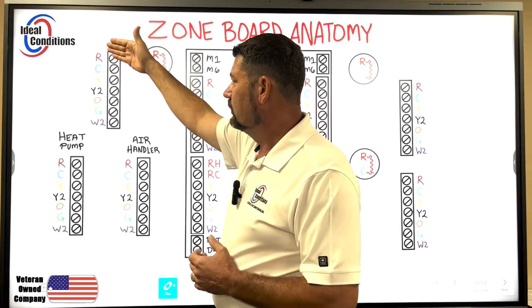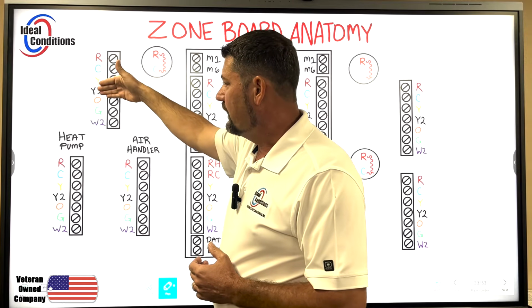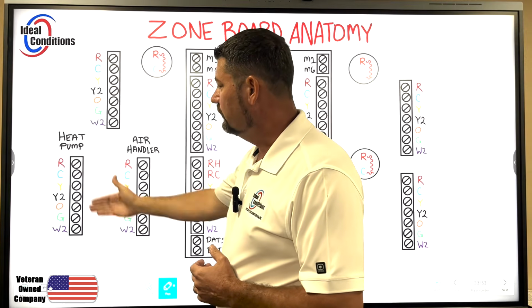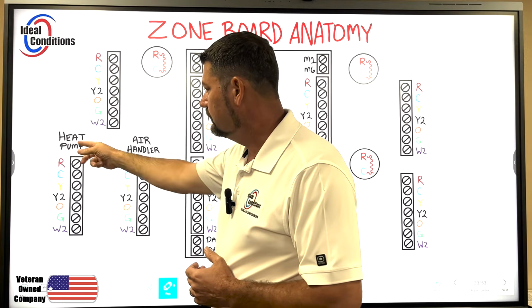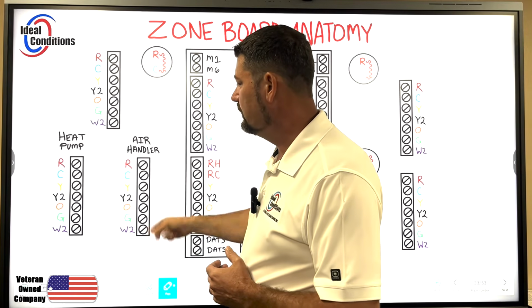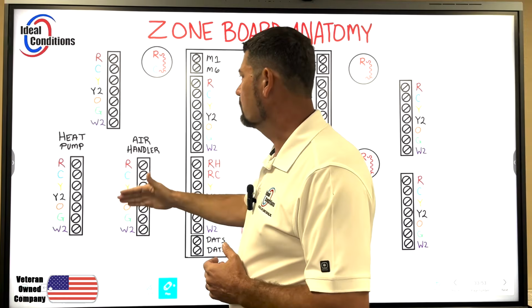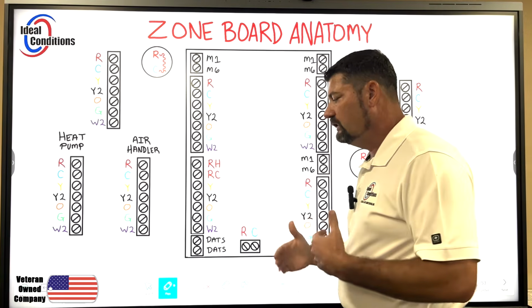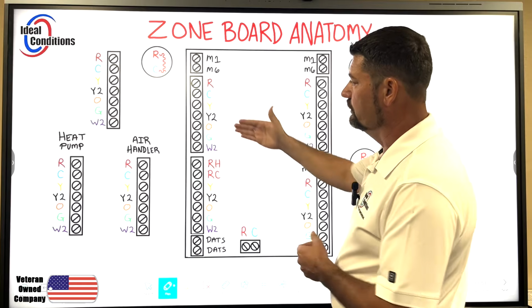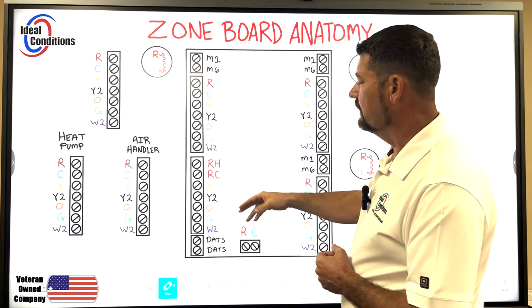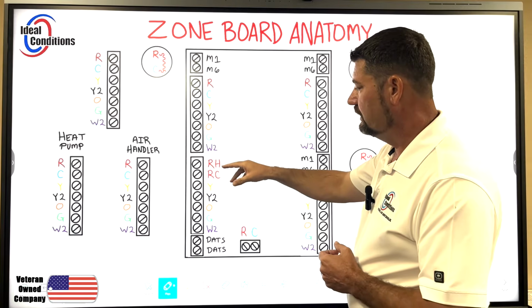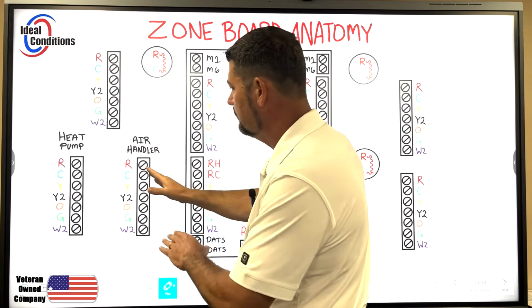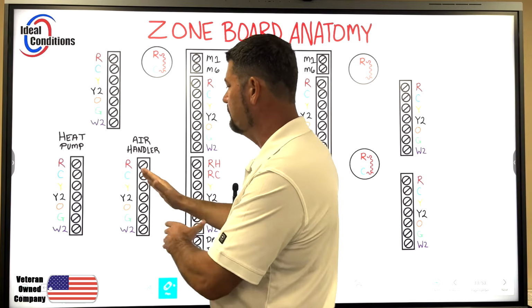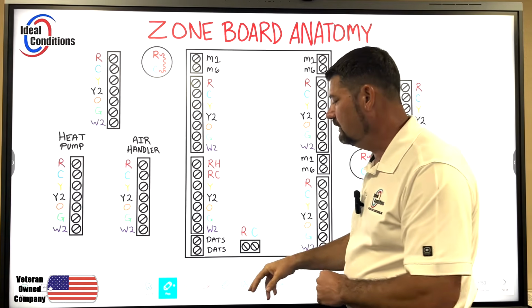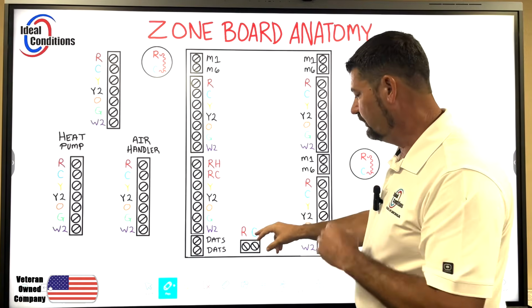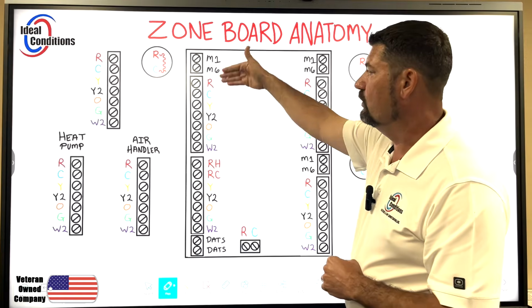We have R, C, Y, Y2, O, G, and W2. The block labeled heat pump and the block labeled air handler have the exact same terminals. I want you to look at this simply, because when we go to the zone board we're doing the exact same thing. Now there are a couple other terminals that aren't exactly like the terminal blocks on the thermostat, the heat pump, and the air handler - we have RH, RC, the DATs, an RC by itself, and we start getting into M1, M6, and so on.